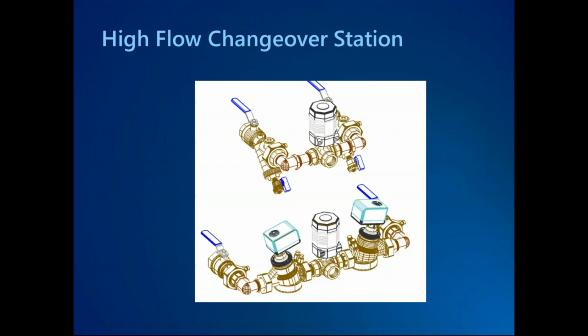First, what we have here is a kit that is just mimicking what we're doing with the 6-way, where we're breaking the 6-way apart and providing 2 3-way valves and all the trim kit associated with it. But if you add up all of the actuators, you will notice that we are back to that 4 actuator scenario. So we aren't really saving any control logic or complexity when it comes to the system design.